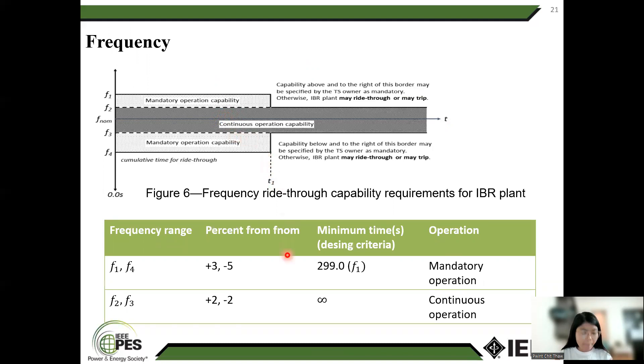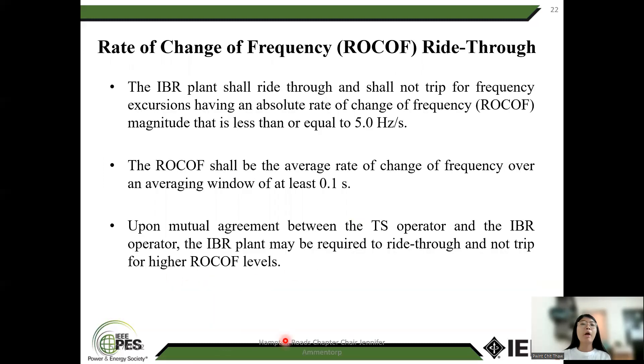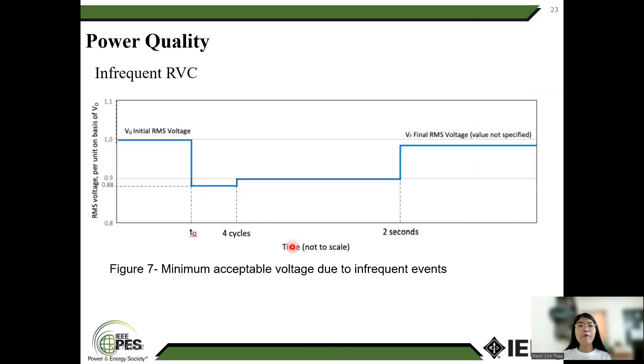The TSO may require additional capacity. F1 and F4: the acceptable limit is plus 3%, minus 5%. F2 and F3: the acceptable limit is plus or minus 2%. Rate of change of frequency ride-through: the IBR plan should ride through for a rate of change of frequency of 5.0 Hz/s. The IBR plan should measure the rate of change of frequency over a averaging window of at least 0.1 seconds. A post-mutual agreement between the TSO and IBR operator may require IBR plans to ride through higher rates of change of frequency.